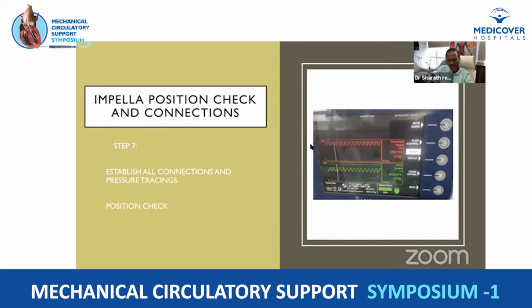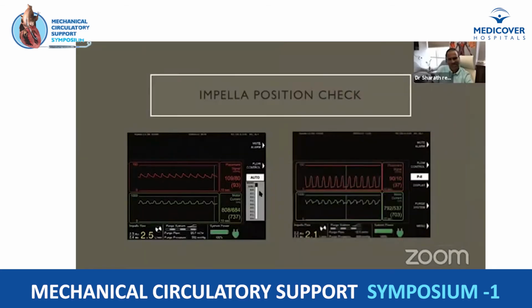So right now the device which is available in India shows only one pressure wave, that is the aortic pressure wave, and the second one is the motor current wave. So this dicrotic aortic pressure wave and this pattern of motor current wave says the position is correct. Once the position is checked, you can establish other connections and purge connections, and then you can move on to beginning Impella.